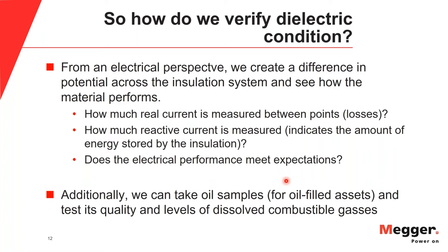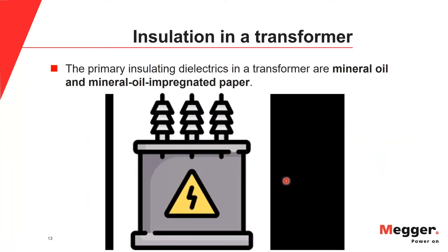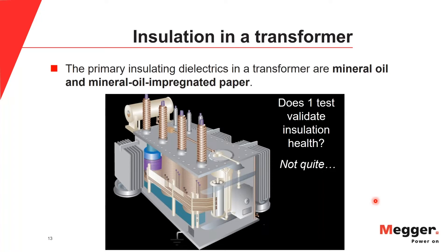The primary insulating dielectrics in a transformer are mineral oil and mineral oil-impregnated paper. If we create a potential difference across the transformer's insulation system, does one test validate insulation health? Not quite. Power factor testing assesses CHL, C-high-to-ground, C-low-to-ground insulation components, as well as C1 and C2 in a bushing. It is helpful to look at each of these systems in the transformer, and then assess what other systems remain that aren't accounted for in a power factor test.